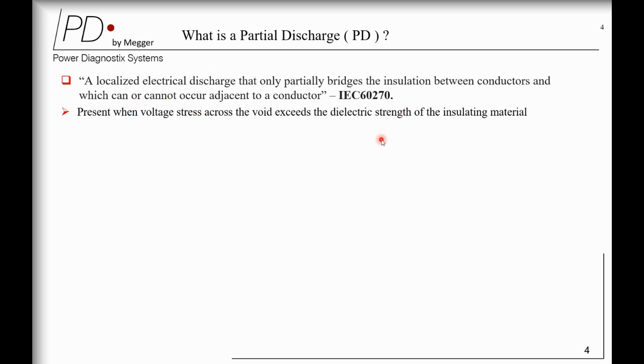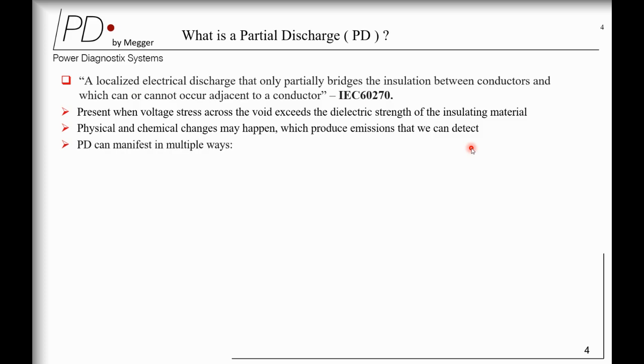Before we move on, what is the GIS PD monitoring system, or what is the PD measurement in GIS? Let's see what partial discharge is, because without the basics there's no logic to it. As per IEC 60270, it is a localized electrical discharge that only partially bridges the insulation between conductors and which can or cannot occur adjacent to the conductor. That means whenever there are impurities in your insulation, let's say a void, and the high voltage stress exceeds the dielectric strength of the insulation material, there are physical and chemical changes that produce emissions that can easily be detected in different PD ways.